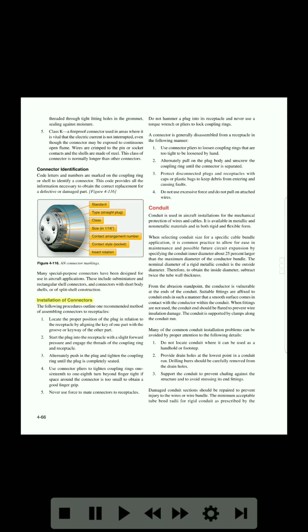Installation of connectors. The following procedures outline one recommended method of assembling connectors to receptacles. 1. Locate the proper position of the plug in relation to the receptacle by aligning the key of one part with the groove or keyway of the other part. 2. Start the plug into the receptacle with a slight forward pressure, and engage the threads of the coupling ring and receptacle. 3. Alternately push the plug and tighten the coupling ring until the plug is completely seated. 4. Use connector pliers to tighten coupling rings a 1/16 to 1/8 turn beyond finger tight, if space around the connector is too small to obtain a good finger grip. 5. Never use force to mate connectors to receptacles. Do not hammer a plug into its receptacle, and never use a torque wrench or pliers to lock coupling rings.